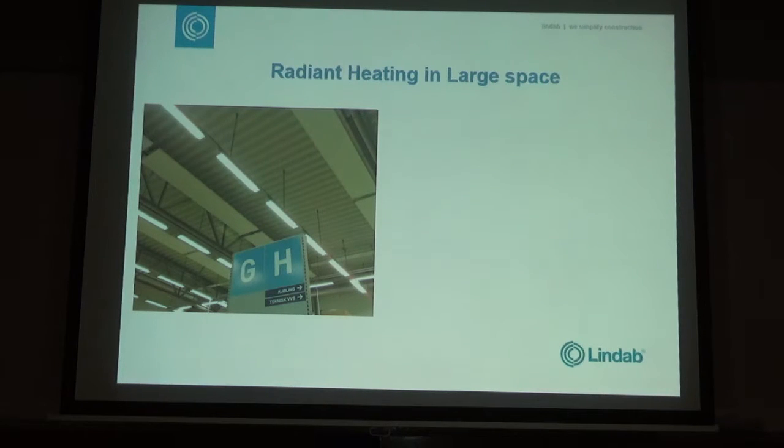Oh, just a quick one. We've talked a lot about mounting heights. Radiant heating, low pressure hot water radiant heating, is really, really effective in high bay areas. I've done 70 degree mean water, I've done 32 metre mounting height. And what happens, the intensity isn't so strong, but it still warms the surfaces up because hot still goes to cold, so it still works at that temperature.